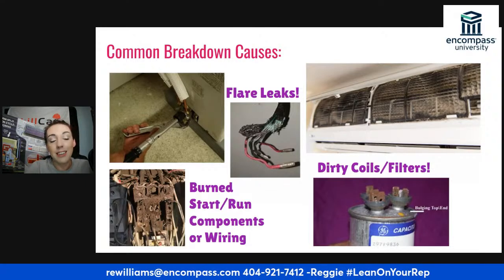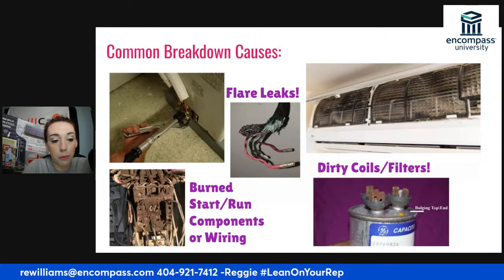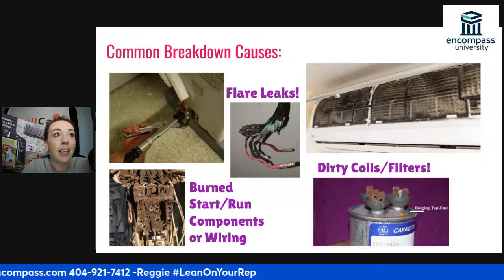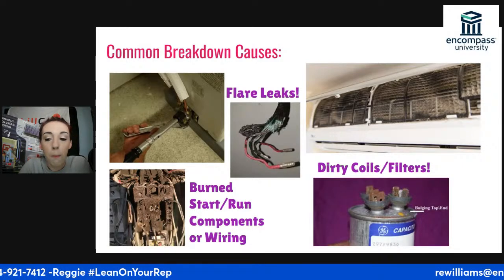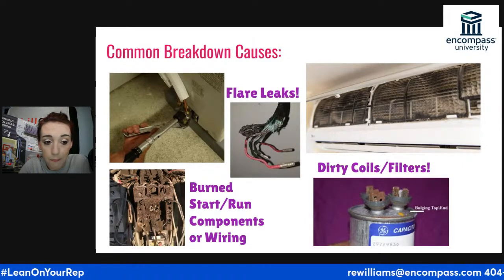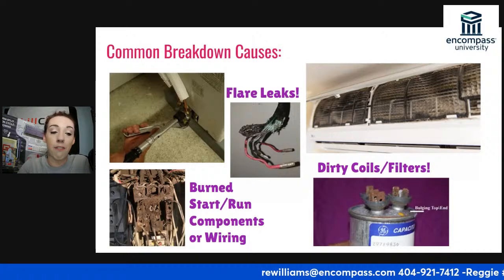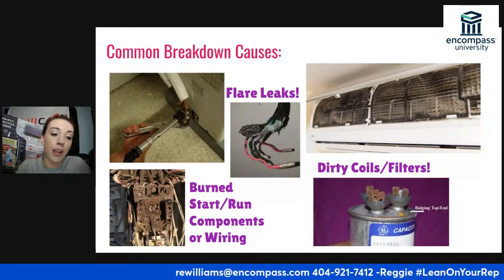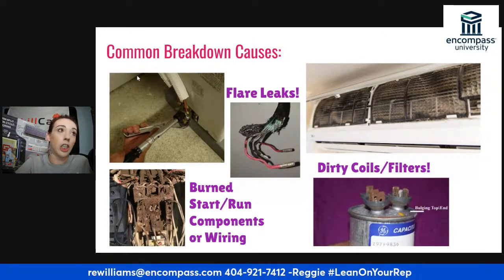So one key difference in the way that we install mini splits, and this is where we get into the install part, is flared connections. Mini splits, you can't braze them. They don't typically have filter dryers on them. And the reason for that is that we have these flared connections.